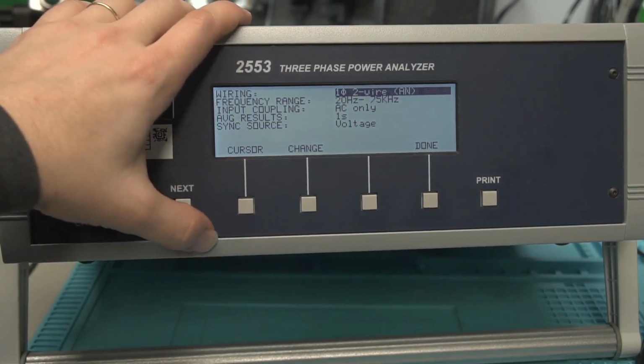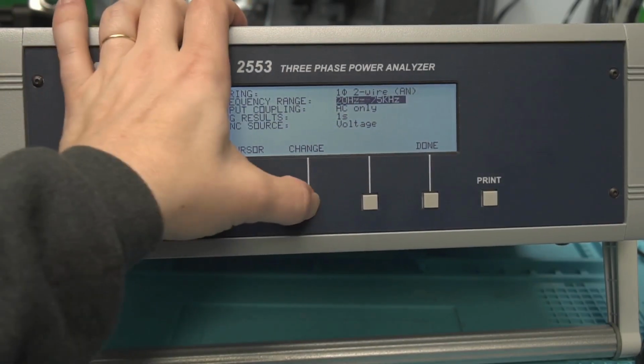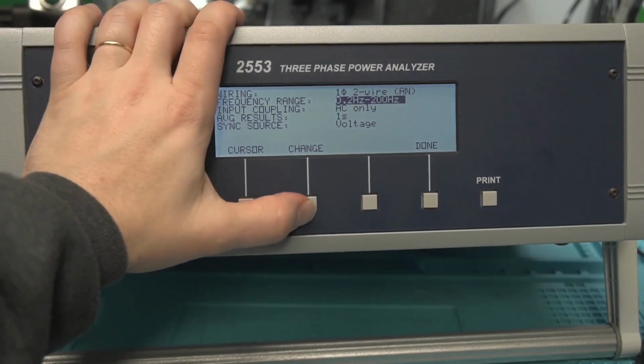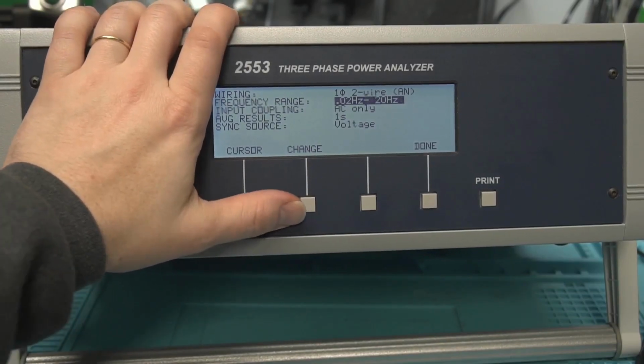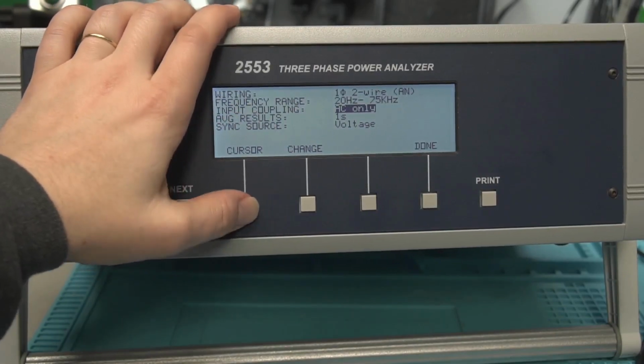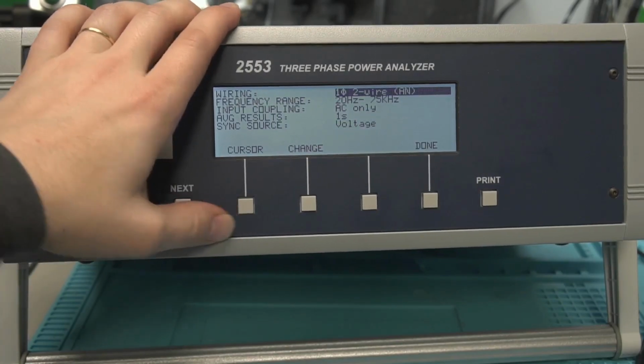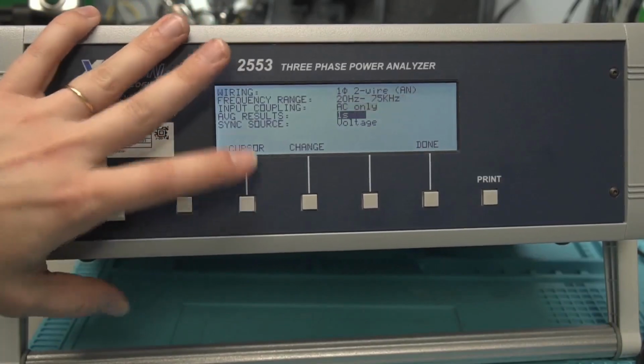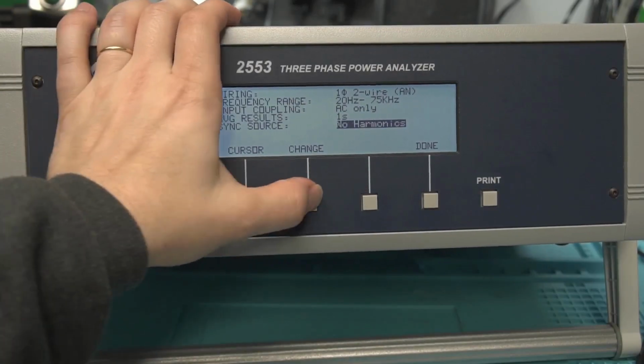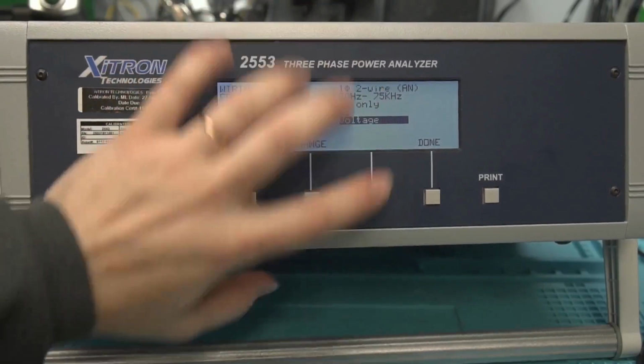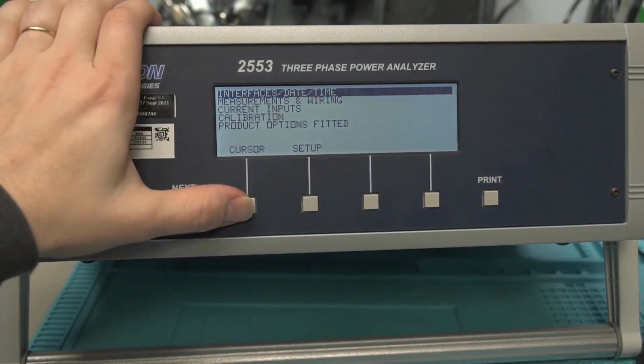And then 20 hertz to 75 kilohertz is the next one. You can change the range there as well. Got 20 hertz to 5 kilohertz, 2 hertz to 2 kilohertz, and 0.2 to 200, and 0.2 to 20. So we'll just leave it at that. AC only, averaging some results, and the sync source. So you can change what you're syncing on. You can sync on current and a couple of other things. 50 hertz, 60 hertz, 400 hertz, no harmonics. Okay, so that's done with the settings in that menu.